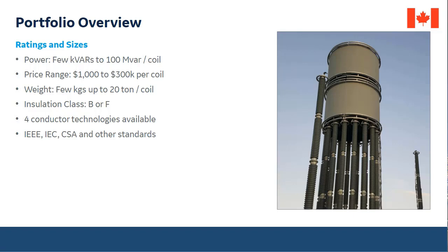I'll select one more question as we are running out of time. So let me see, how do we calculate the MVAR rating for the reactors? I think this question may have two different answers. The first answer, the simple one, is that you can calculate the MVAR rating basically by multiplying the impedance by the current to the power of two. That basically gives you the power rating of that coil.